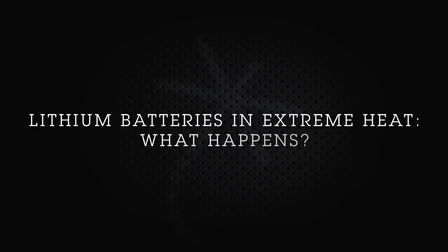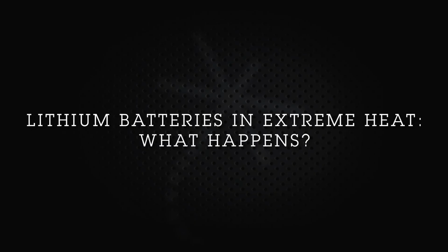Can lithium-ion batteries be operated in extreme heat? Well, they can be operated hot. Actually, if you're operating over 100 degrees Fahrenheit, the capacity of the battery will increase. But this comes at the expense of faster degradation. So if you're consistently operating over 90 to 100 degrees Fahrenheit, rather than getting 3,000 complete cycles with 20% degradation, that 20% degradation will happen sooner.